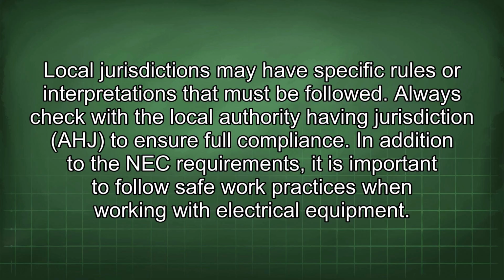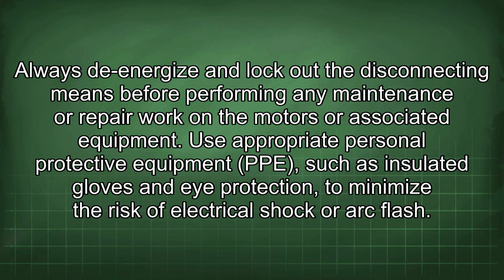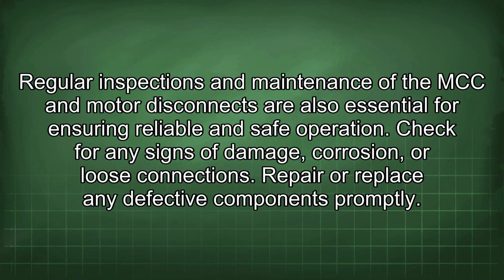In addition to the NEC requirements, it is important to follow safe work practices when working with electrical equipment. Always de-energize and lock out the disconnecting means before performing any maintenance or repair work on the motors or associated equipment. Use appropriate personal protective equipment (PPE), such as insulated gloves and eye protection, to minimize the risk of electrical shock or arc flash.